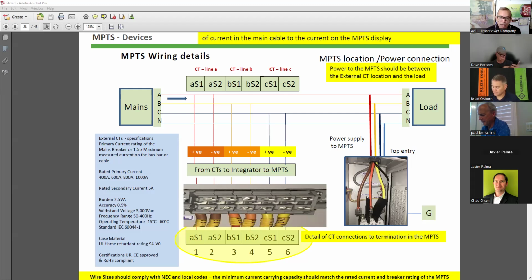What if you have only 1 amp coming on it? Because you have a 500 amp CT and you are only off peak, you're at 100 amps. So that 100 amps now is only at 1 amp at the source. And then MPTS is sitting 300 feet away. Does that 1 amp even reach the MPTS?